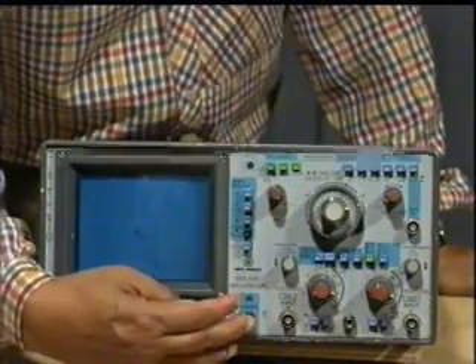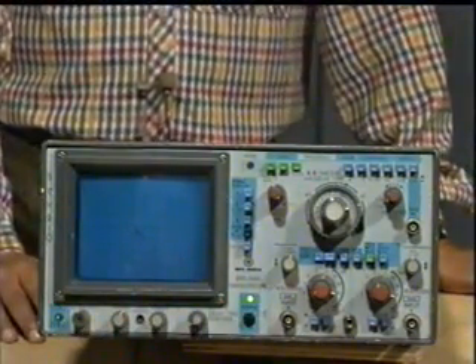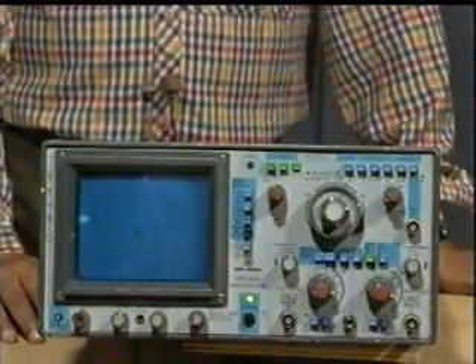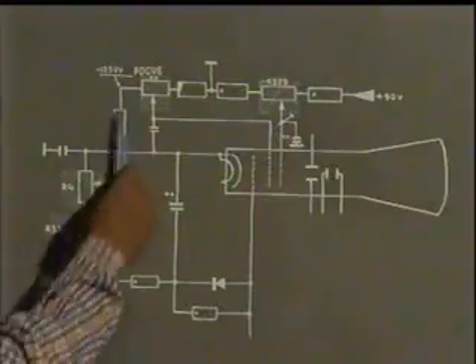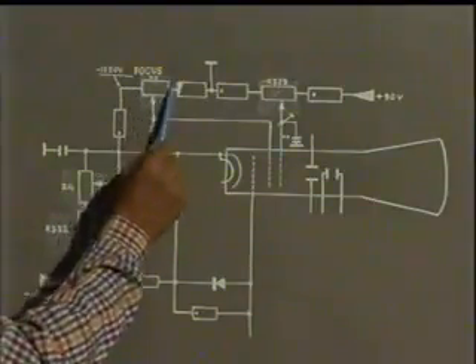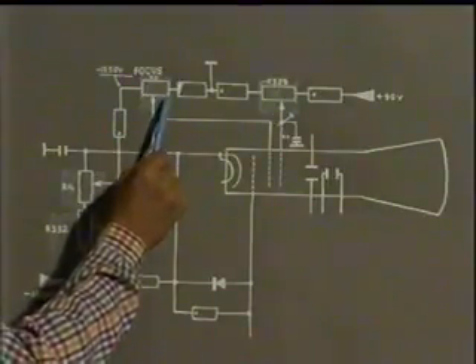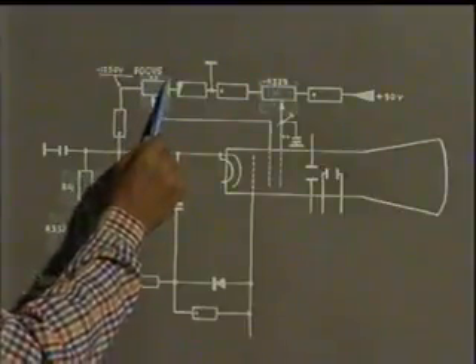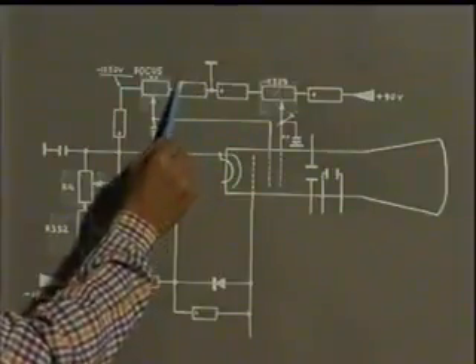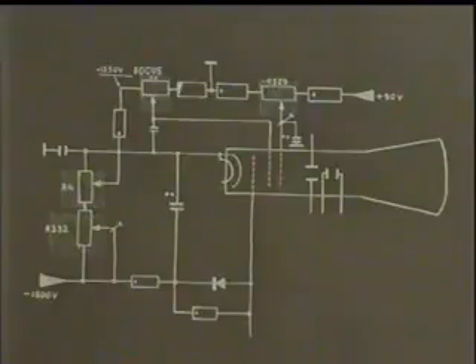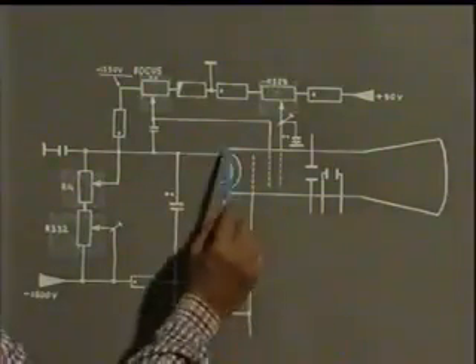Here we have another oscilloscope which has the problem of focus, and this problem of focus may be due to open focus control potentiometer or open bleeder resistance or bad CRT. Let us see this CRO. Here the beam of this CRO is defocused. The focus control potentiometer in this diagram is here. And the focus problem in oscilloscope is mainly because of this open focus control potentiometer or the open bleeder resistance. In certain situations, the focus problem may be the bad CRT.